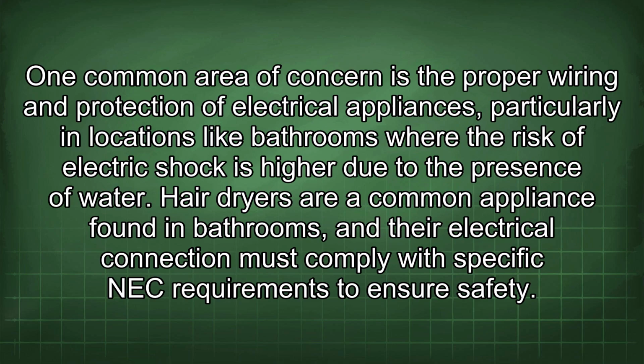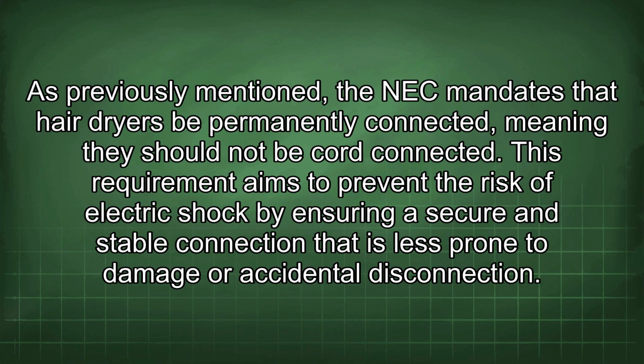One common area of concern is the proper wiring and protection of electrical appliances, particularly in locations like bathrooms where the risk of electric shock is high due to the presence of water. Hairdryers are a common appliance found in bathrooms, and their electrical connection must comply with specific NEC requirements to ensure safety. As previously mentioned, the NEC mandates that hairdryers be permanently connected, meaning they should not be cord connected. This requirement aims to prevent the risk of electric shock by ensuring a secure and stable connection that is less prone to damage or accidental disconnection.